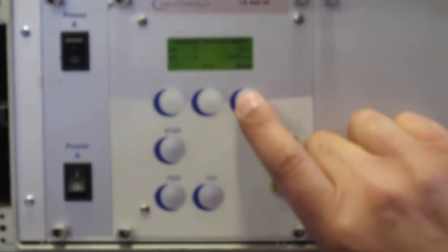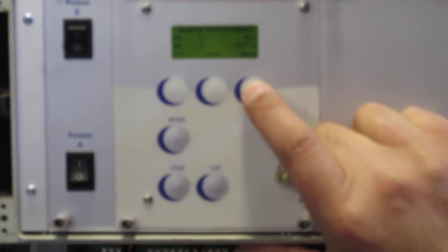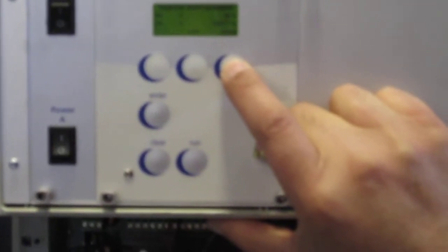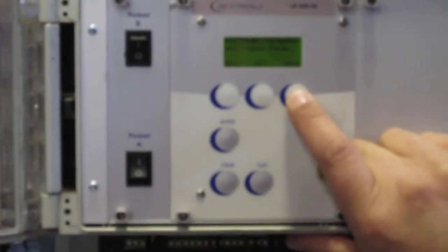So you just clear that, and then now when I do a recalibration today, you'll get a new source decay date. When the source gets so low on counts, it says, okay, your source is going dead, you better do something soon. With 30 years, it will probably tell you a year ahead of time or whatever. You probably get 2 half-lives out of your source, pretty close, at least 1.5, I'd say. We try to size them for that.